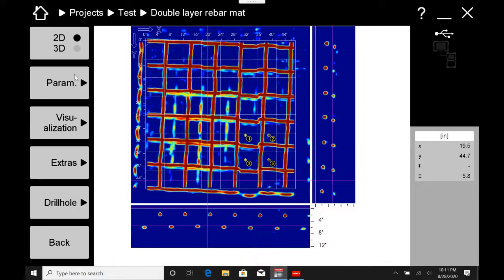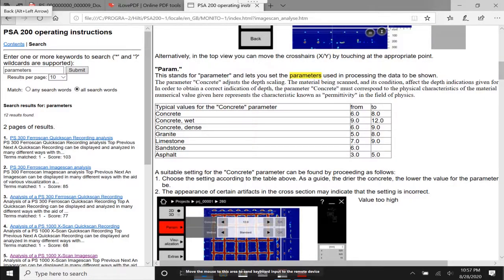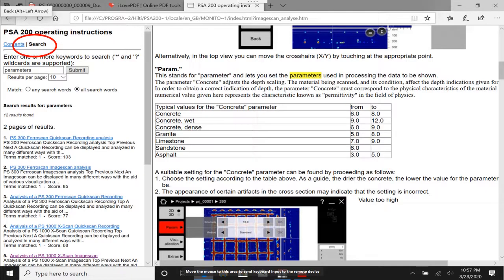The second thing is your parameters. I'm going to click this option. You have the ability to change your dielectric value, which is here. That's a preference for you. And for more information, here is the Help Guide. If you can see, I went to the Search option in the top left corner of the Help Guide, and they just typed in parameters, and it pulled up one of the fifth. The fifth option on the left side of the search results was understanding the parameters in the PS1000 analysis, and you can see that it goes through the different dielectric settings that you want to set for concrete, given your situation. So I recommend you play with this as much as you can to make sure that your depth and your view settings look to the way that you need them in order for you to do your proper analysis of your scan.